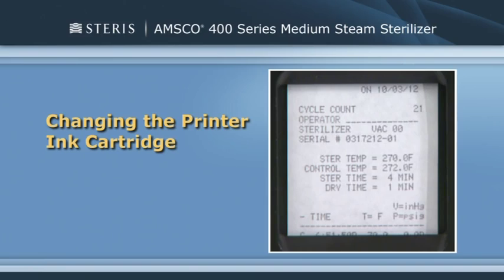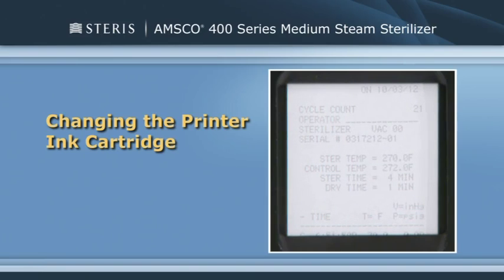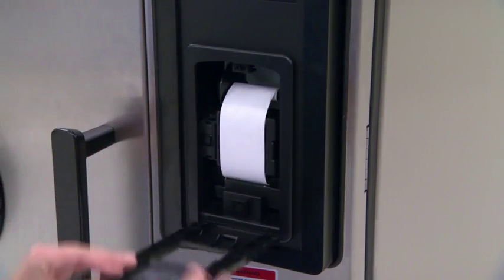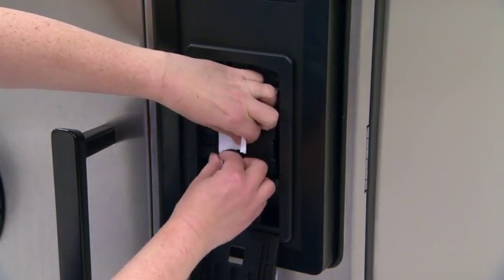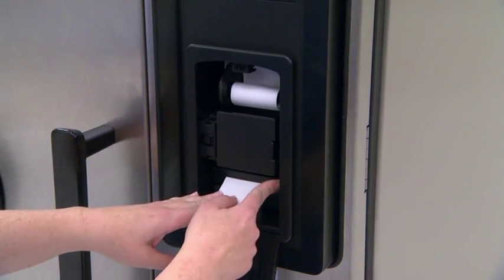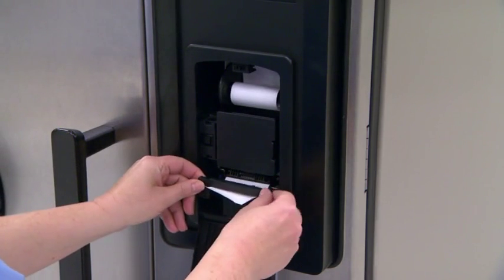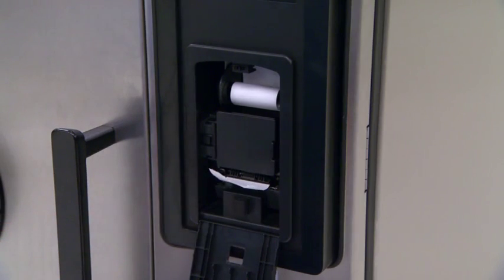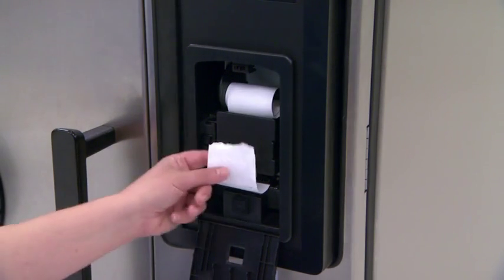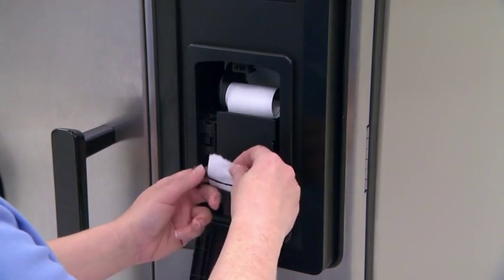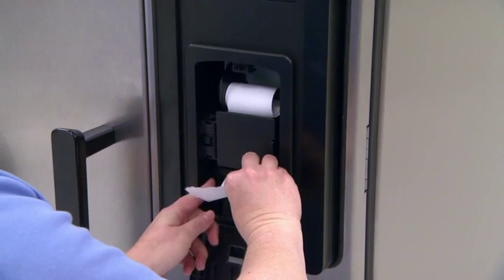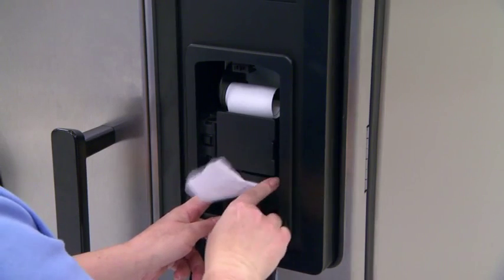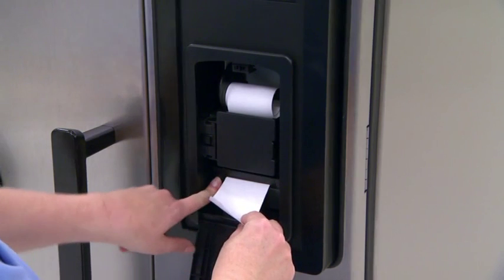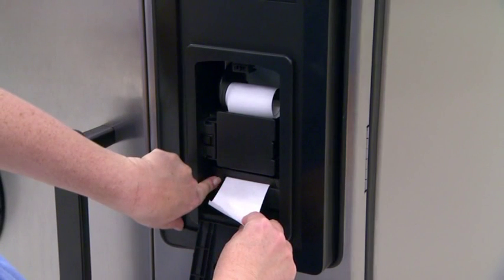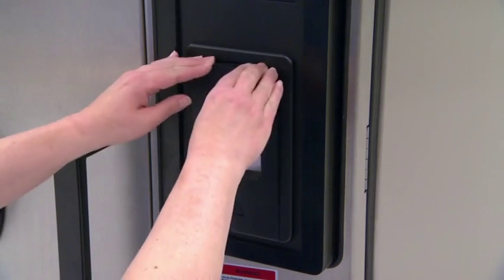The printer ink cartridge should be changed as soon as the type on the printouts is noticeably light or faded, and before printouts become difficult to read. Tear the paper between the take-up spool and the printer. Then press on the right end of the ink cartridge until the left end of the cartridge pops out of the printer. Slip the cartridge off the end of the paper. Slip a new cartridge over the paper, making sure the paper slides between the ink cartridge and ink ribbon. Install the left end of the cartridge first, then push the right end in, snapping it into place. Retighten the ribbon by rotating the wheel on the left side of the cartridge a quarter turn. Close the printer door.